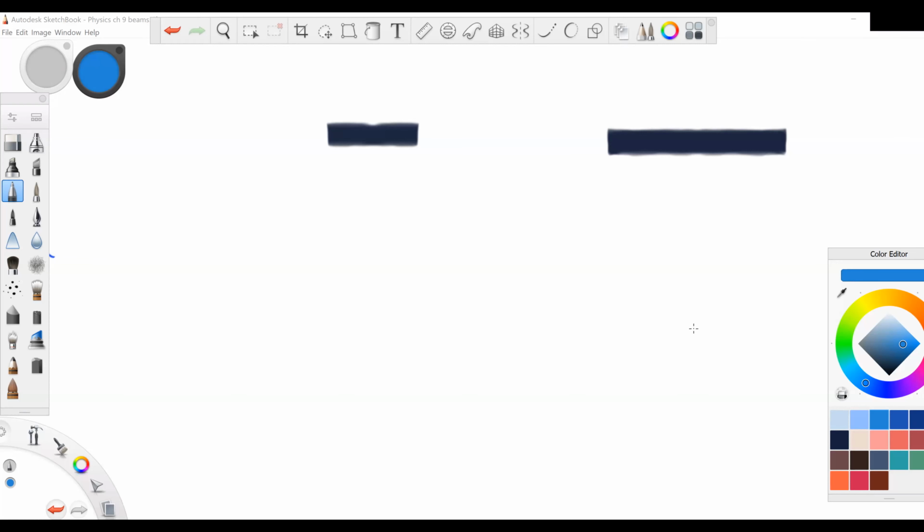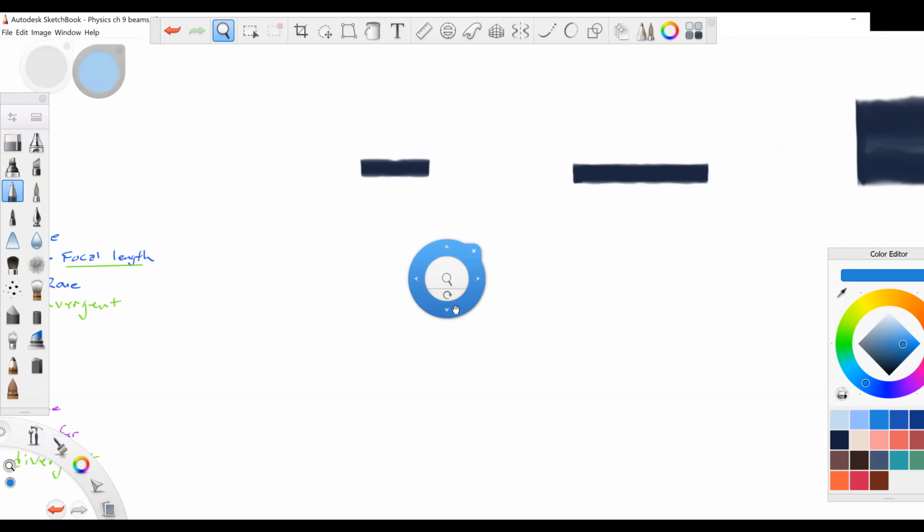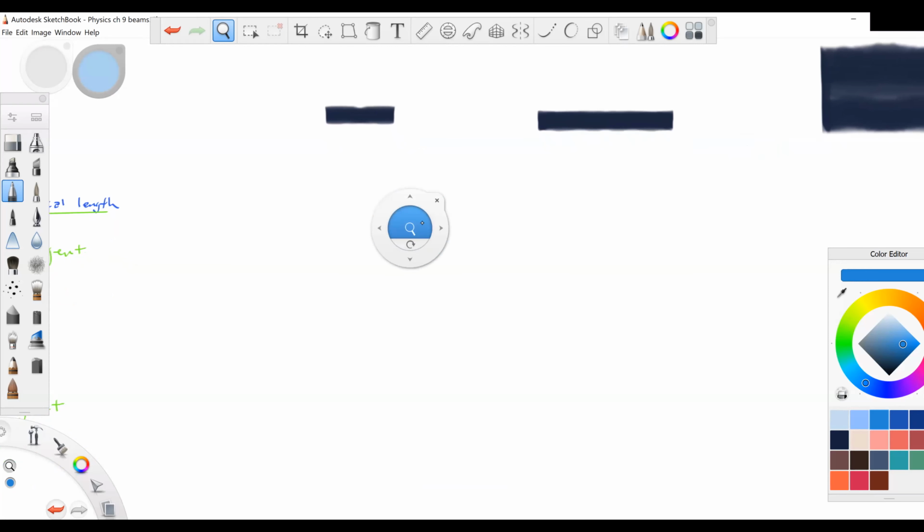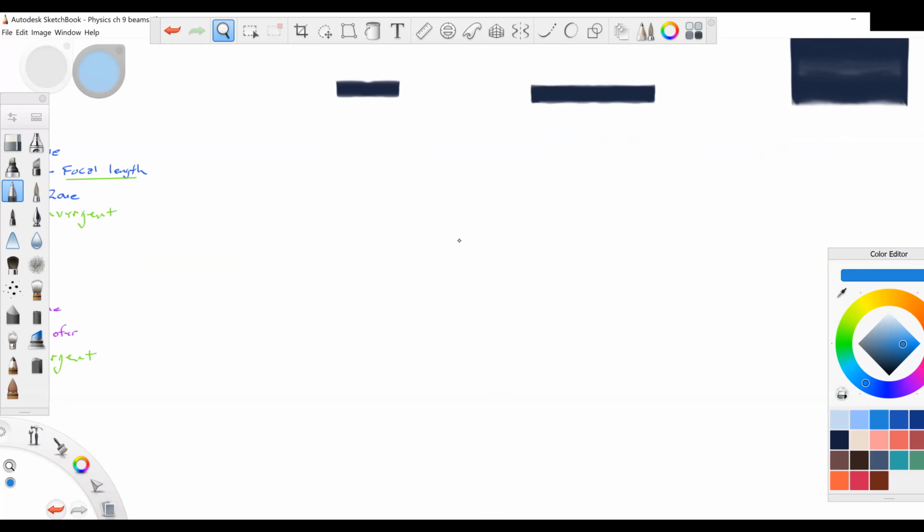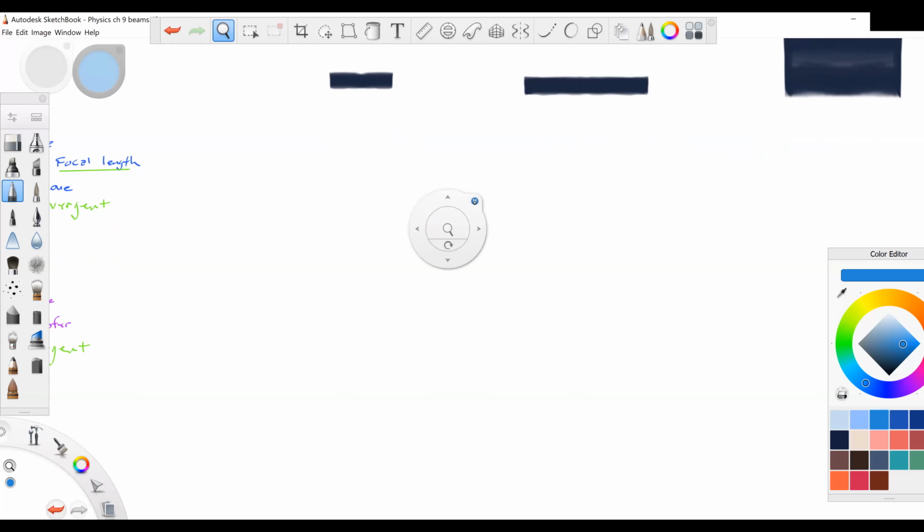So we're going to talk a little bit about the profile of a transducer element, and how that affects the depth of the natural focus. Even though we don't use elements like this, it still matters because aperture, width, and frequency still affect the natural focus of multi-element transducers. That's why we have to learn about single element transducers first.